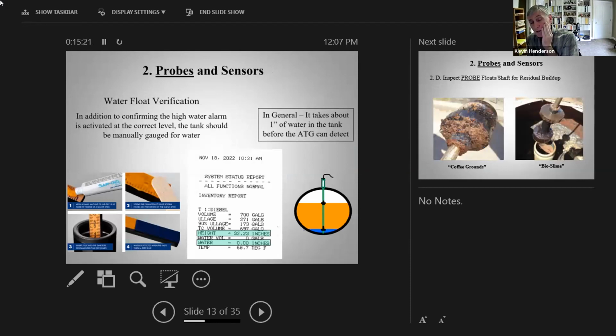The other thing we also always do is we will manually gauge the tank for water. And of course, just water finding paste. And with ethanol fuel, this can be tricky, of course, we all know that. But we do want to make the effort to manually gauge the tank for water. So if you look at the inventory report for Veeder, it will always tell you the water level in the tank. And you see this one, an example is say 0.00 inches, and that's fairly typical. And so when you stick the tank, you want to make sure that there is no water in the tank visible on the gauging stick, but also you have to put a little caveat on that. This is something that not everybody realizes about tank gauges. And it's not just limited to Veeder.